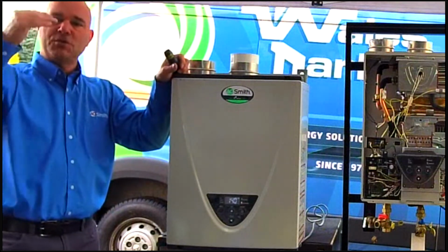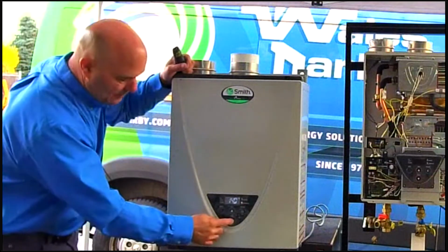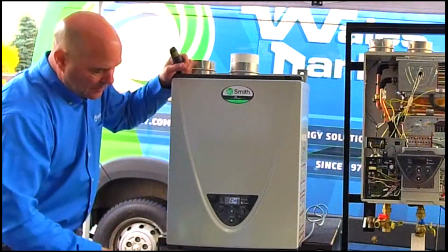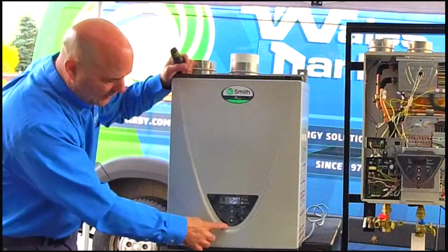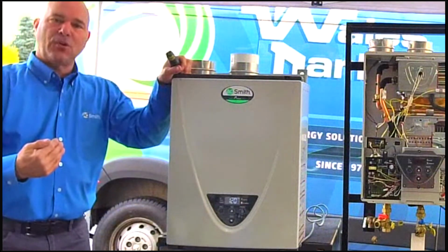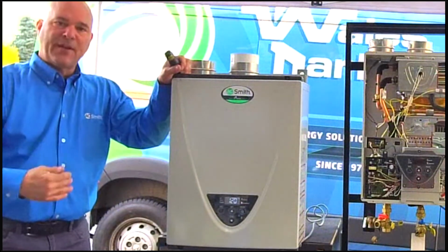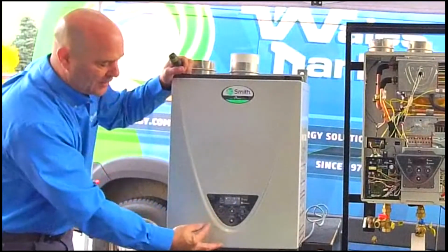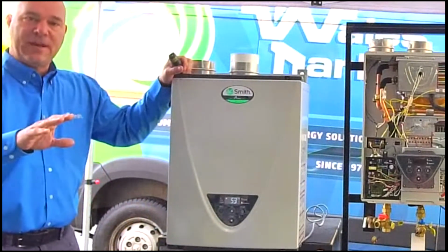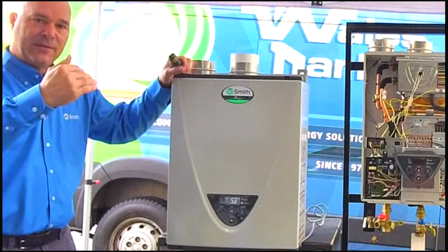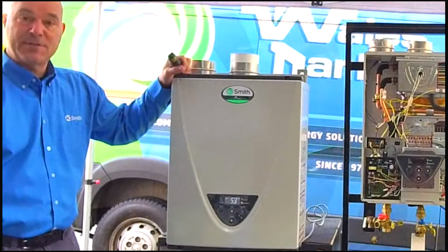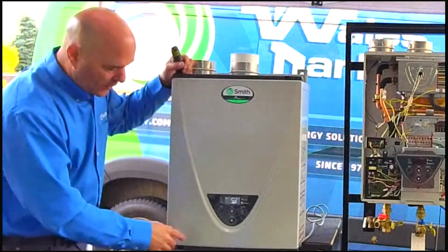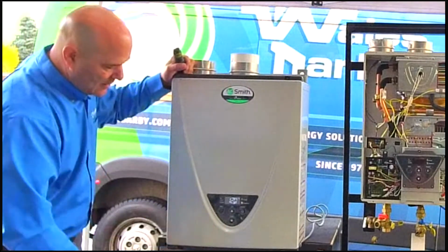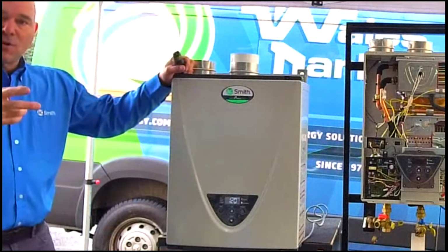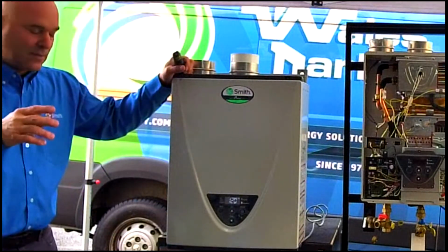Now I can live within that 120 to 140 range by making an adjustment. But if I take that down below 120, that kicks me out of the controller again. So if I want to go back above 120, I would have to push that info and hot button again, hold them down for 3 to 5 seconds until it allows me to go back into the control and step up to those hotter temperatures. But we feel 120 out of the box is a good number. So that's my controller as far as up and down for temperatures. Pretty simple.